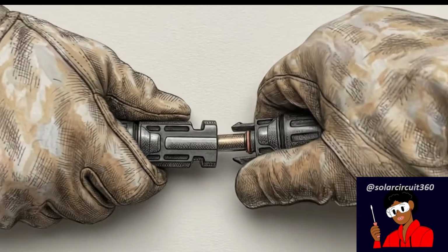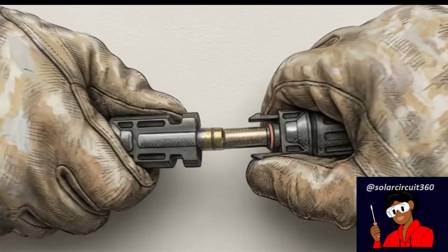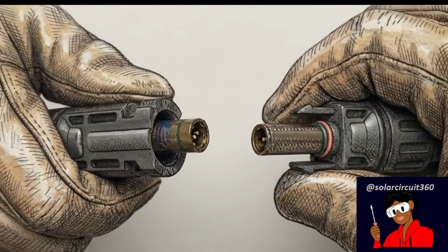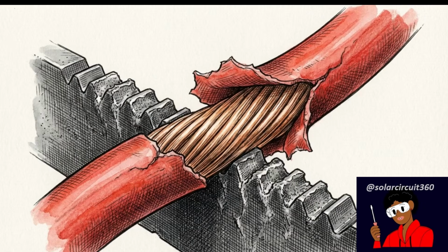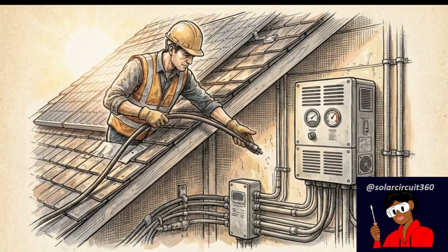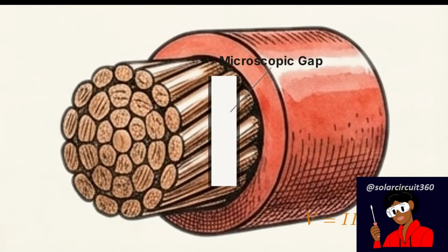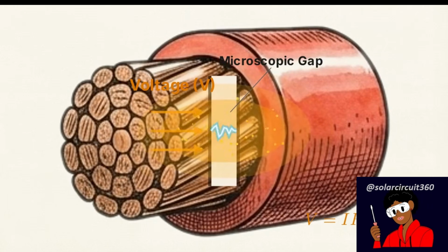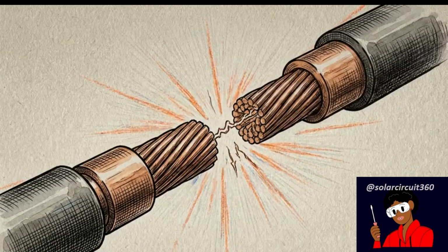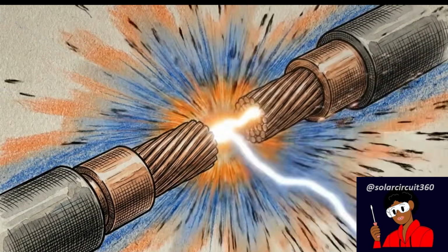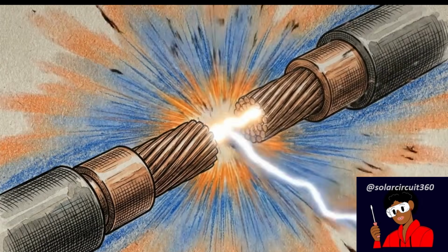All it takes is a microscopic physical gap in the circuit to compromise the system. This gap forms when a connector is loose, when wire insulation gets scraped, or when an installer makes the fatal error of unplugging a live cable under an active load. This diagram shows the Ohm's law dynamics taking place at that microscopic gap. High voltage acts as immense pressure, forcefully pushing current to leap across the physical separation. That forced jump superheats the surrounding oxygen, altering empty space into a highly conductive pathway. Massive current is not a prerequisite here. High voltage alone possesses the raw force required to initiate a destructive arc fault.